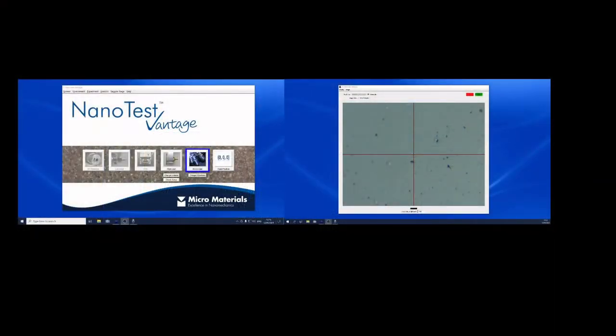So if we come to the computer screens, we've got 2 windows of interest here. One of them is the main NanoTest software screen, which is a nice, intuitive, simple interface to use. And the other one is the microscope image screen, so we can actually see the surface of the sample here on the microscope screen. So this blue box here around this microscope position just tells us that currently our sample stage system is at the microscope.